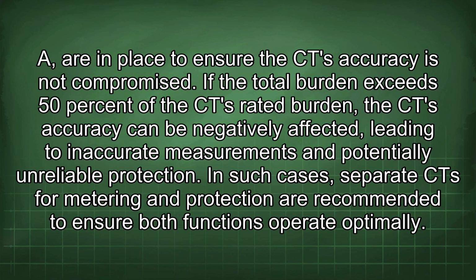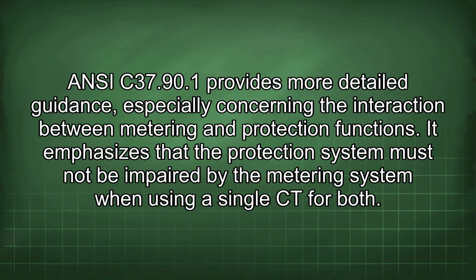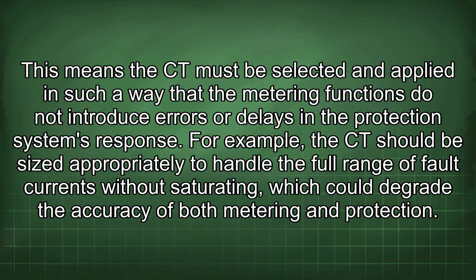In such cases, separate CT for metering and protection are recommended to ensure both functions operate optimally. ANSI C37.91 provides more detailed guidance, especially concerning the interaction between metering and protection functions. It emphasizes that the protection system must not be impaired by the metering system when using a single CT for both. This means the CT must be selected and applied in such a way that the metering functions do not introduce errors or delays in the protection system's response.